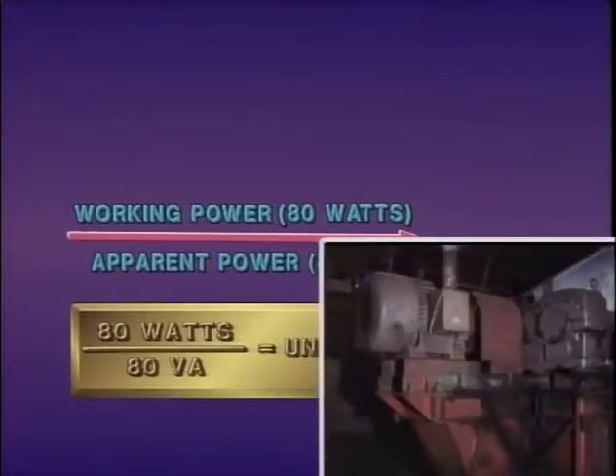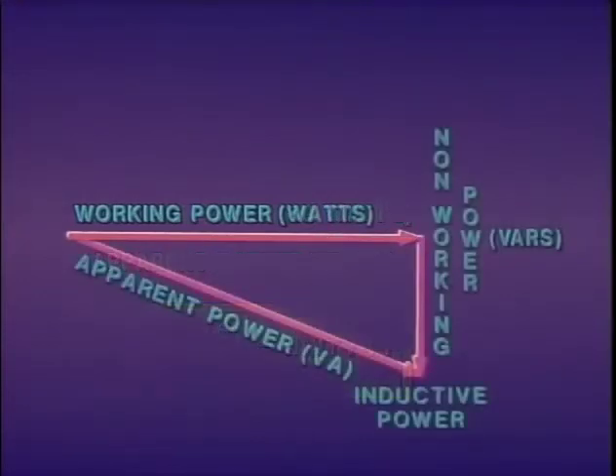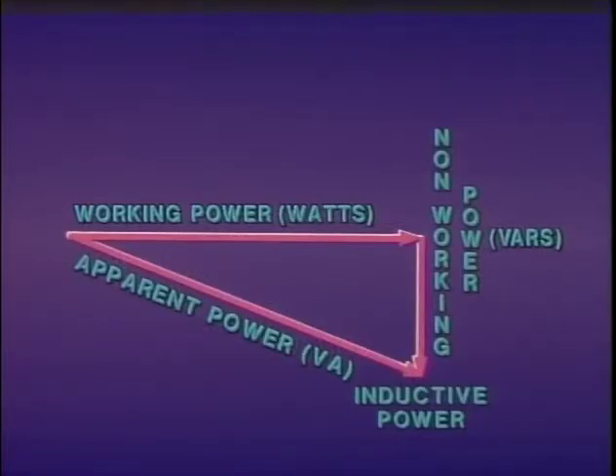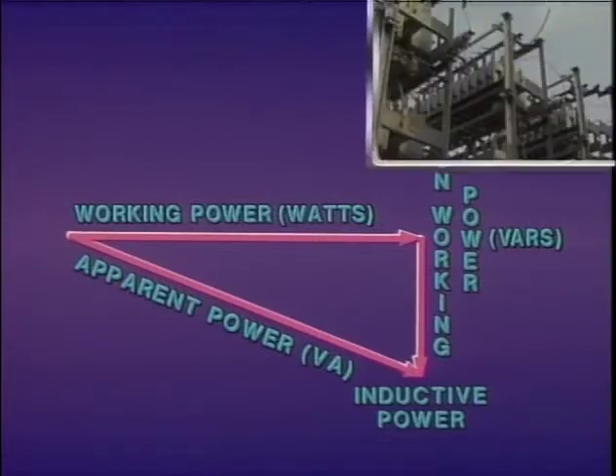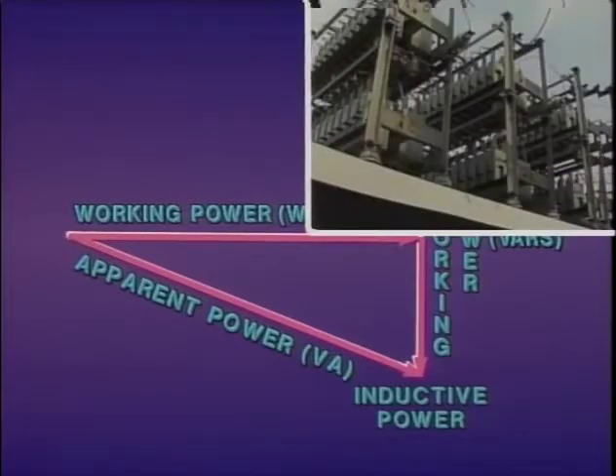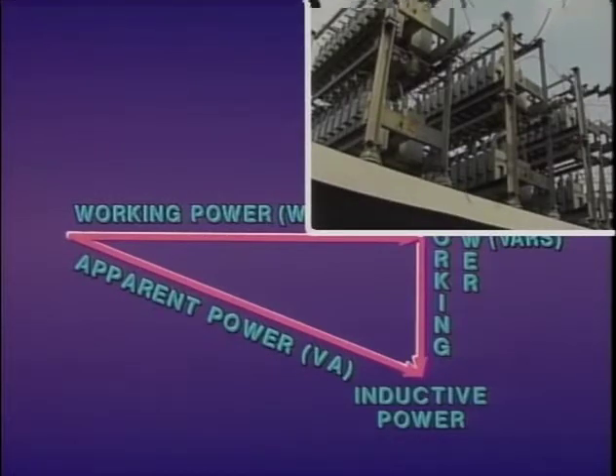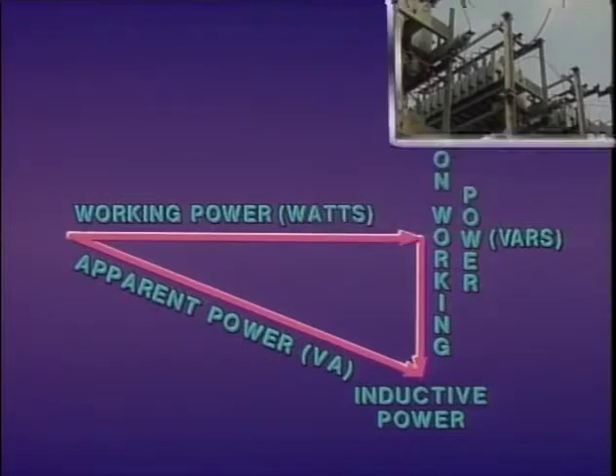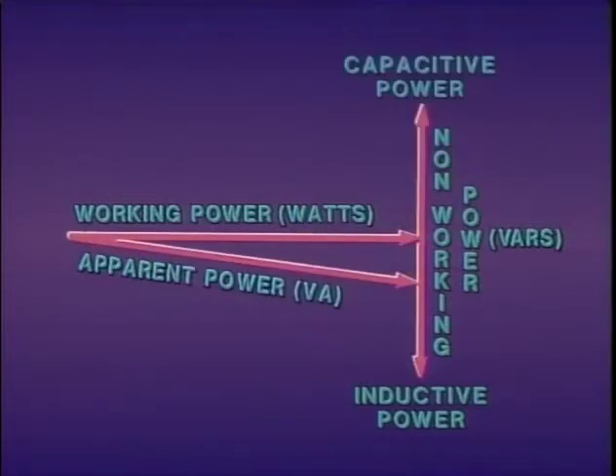For example, in today's power systems it is common for the combined effect of many motors to create an excessive demand for non-working inductive power. Excessive demand for non-working inductive power results in a lower power factor than is desirable — the utility has to provide more power than is actually needed to perform useful work. However, rather than increase power output, power factor can be improved by using capacitor banks to offset the excessive demand for inductive power and bring the power factor closer to unity.